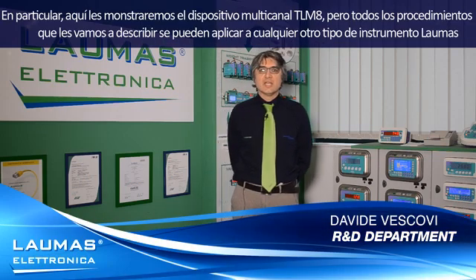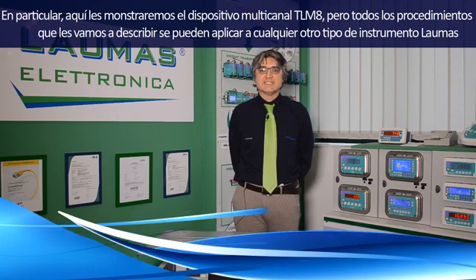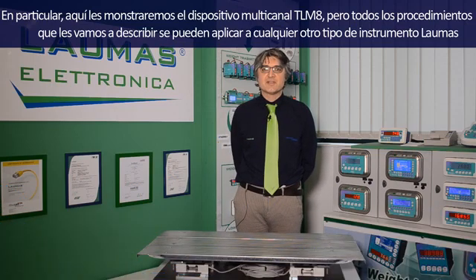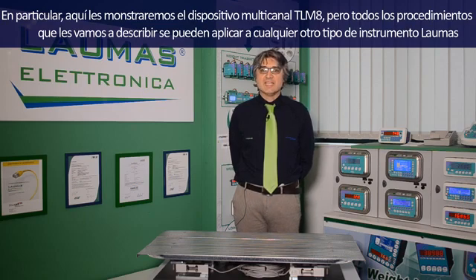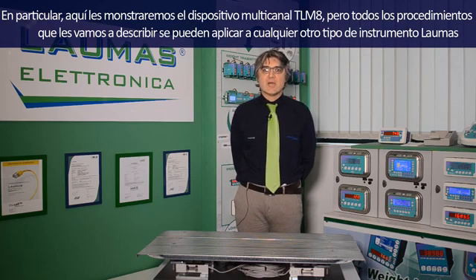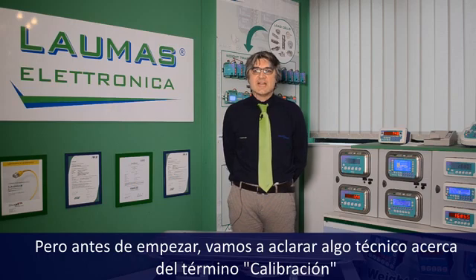Hello, I will now show you how to calibrate a LAUMAS device. In this example, we will use a TLM8, a multi-channel transmitter, but what I'm going to say can be applied to any other LAUMAS device. We will first start with what we call theoretical calibration, which is basically entering into the device nominal values for load cells and system. Before we start, a quick technical note about the word calibration.